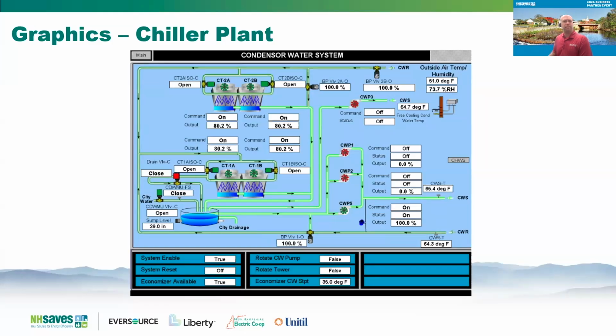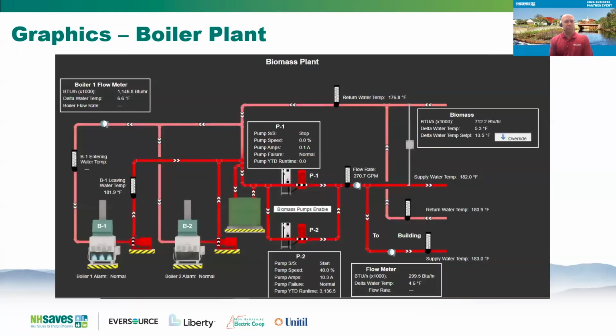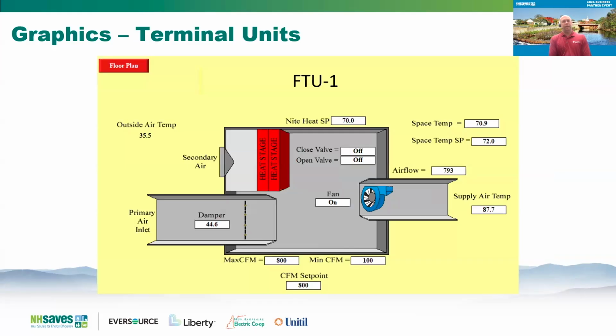Here's an example of a boiler plant. The pretty modern graphic on this one. So again, lots of points. You can see the pumps, you can see the differential pressures, set points, everything. A lot to garner from these graphics. Now switching to the terminal units. So this is an example of the antiquated fan-powered box that went with the floor plan and the rooftop unit I showed previously. Again, this has actually got a lot of the information that you would expect to see for a terminal unit, just not as pretty graphics.